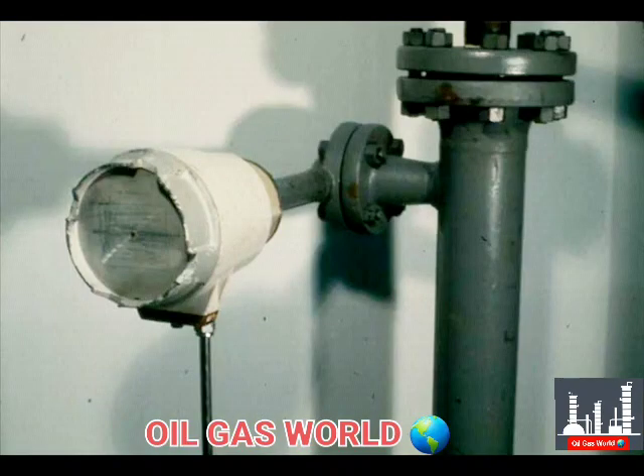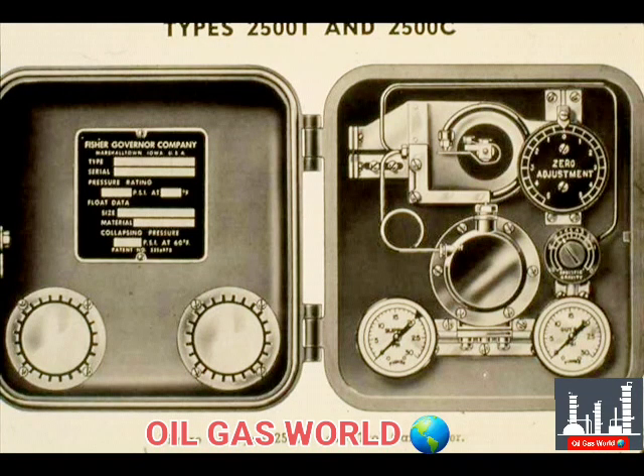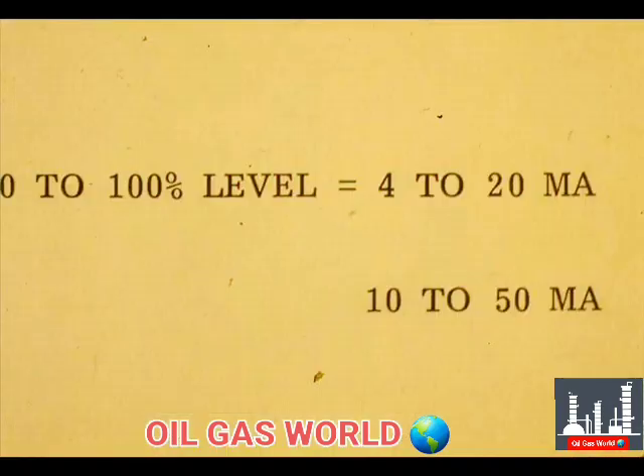This lesson will teach operating principles and terminology associated with displacer type electronic level transmitters. An electronic level transmitter is a device that converts a liquid level into a proportional direct current signal. A zero to 100 percent level may be converted to a 4 to 20 milliamp signal or a 10 to 50 milliamp signal.